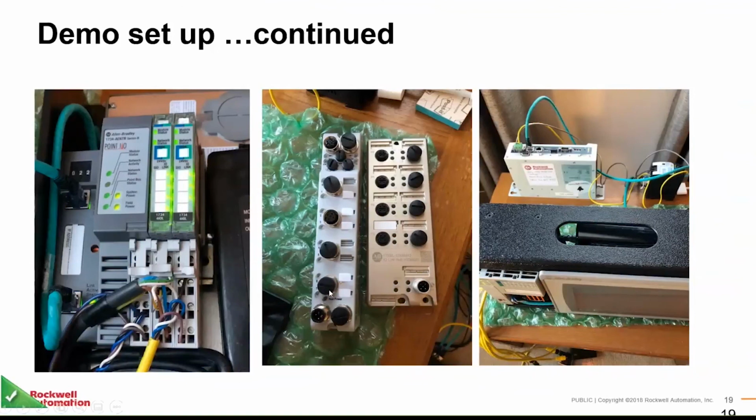So now with 1 point, you are monitoring 16 devices there. Huge cost reduction, huge wiring reduction in installations, IO reduction and wiring reduction. However, the big thing to be noted is there is no diagnostics coming back. So all the goodness which comes with the diagnostics for preventive maintenance is not there when you're using an IO-Link hub. However, there are places where it can be used where diagnostics is not needed.